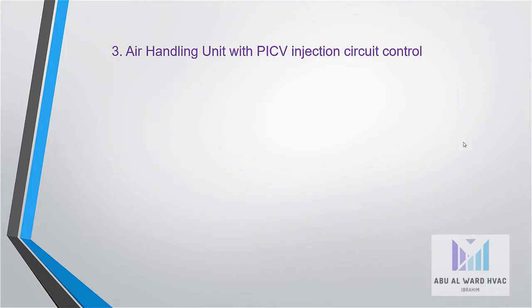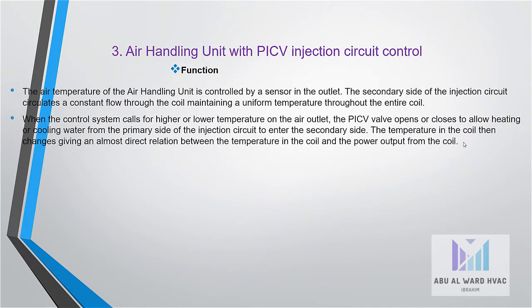In air handling units with PICV injection circuit control. The function: the air temperature of the air handling unit is controlled by a sensor in the outlet. The secondary side of the injection circuit circulates a constant flow through the coil, maintaining a uniform temperature throughout the entire coil. When the control system calls for higher or lower temperature on the air outlet, the PICV valve opens or closes to allow heating or cooling water from the primary side of the injection circuit to enter the secondary side. The temperature in the coil then changes, giving an almost direct relation between the temperature in the coil and power output from the coil.